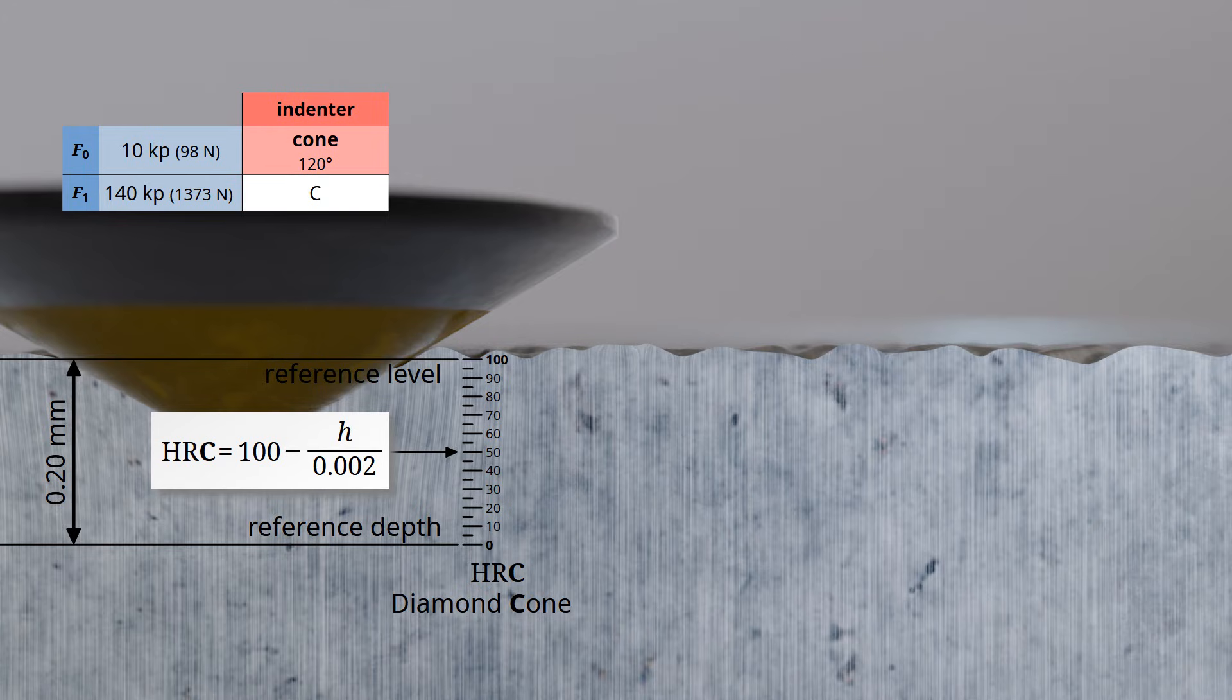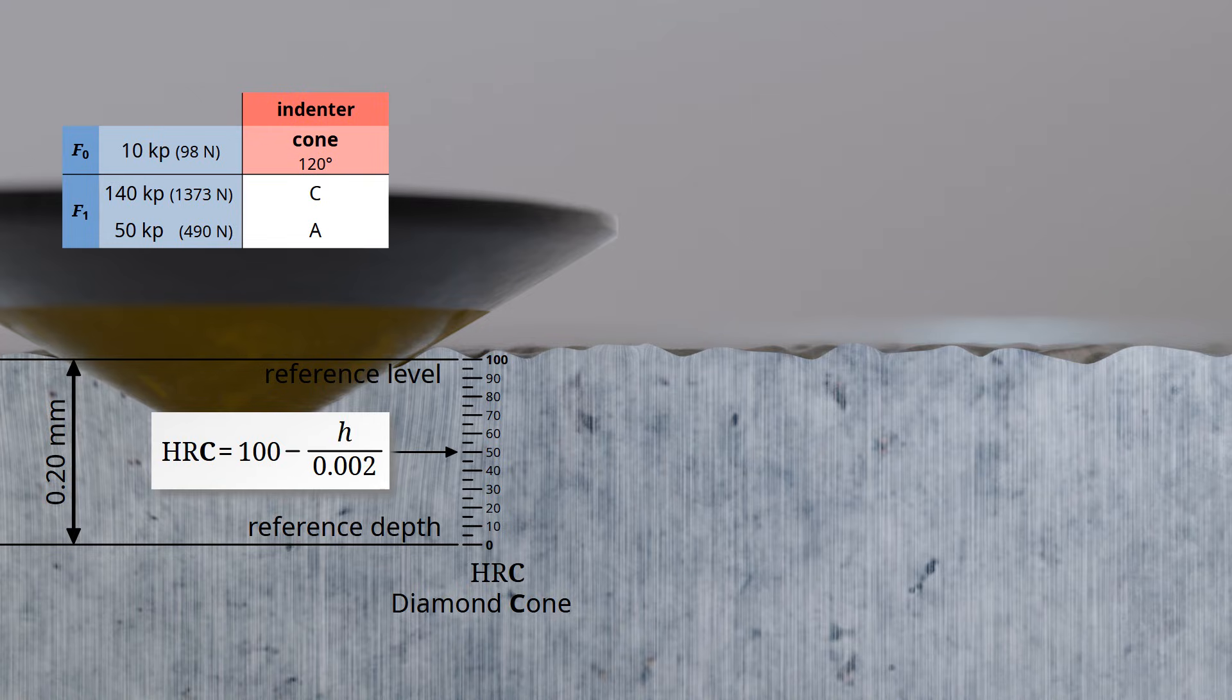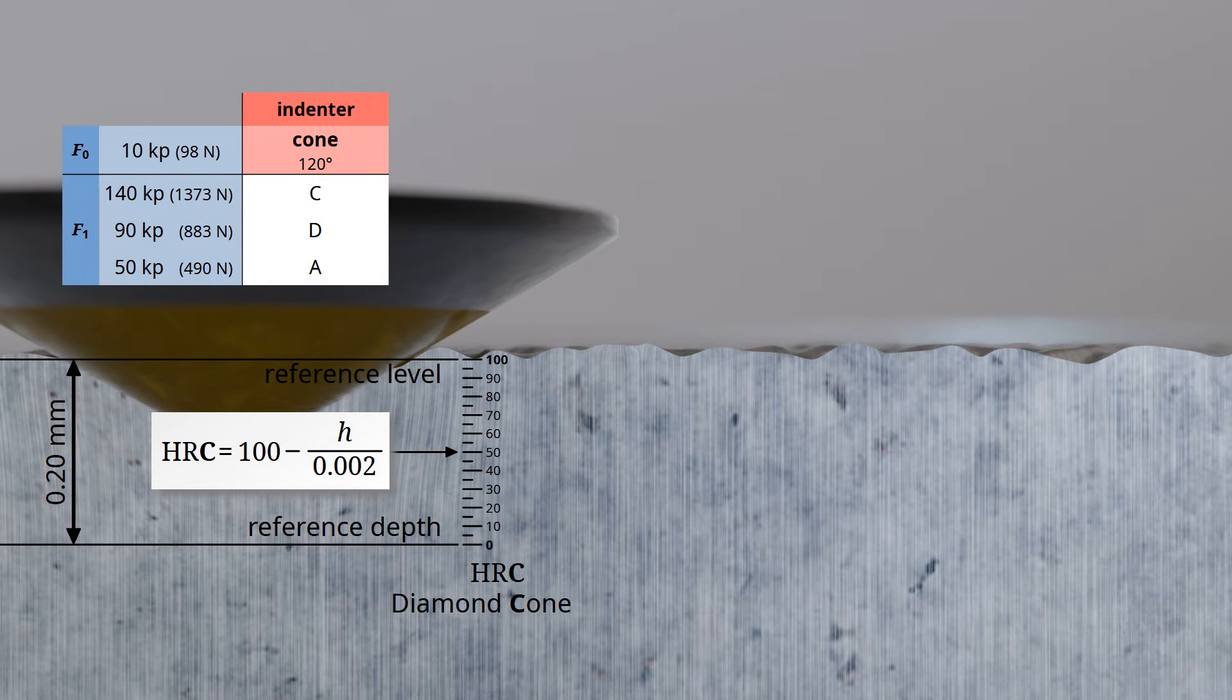However, especially when testing thin sheets, there is a risk that such high test forces may cause the material to bulge out on the opposite side, thereby falsifying the measurement result. To address this, the test variant scale A was introduced for diamond cone testing, which uses a reduced test force of 50 kiloponds, equivalent to 490 newtons. There is also a less common variant scale D, in which the hardness value is determined using a test force of 90 kiloponds, equivalent to 883 newtons. For test variants C, D, and A, the hardness value is calculated using the provided formula.